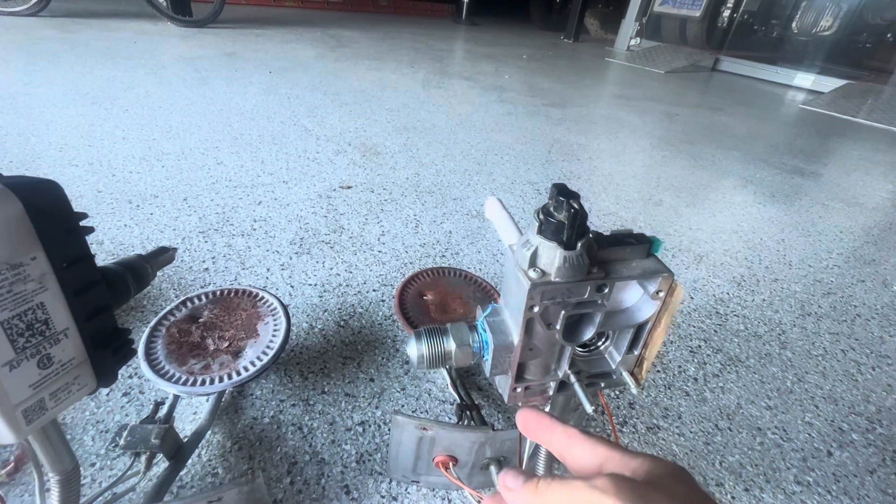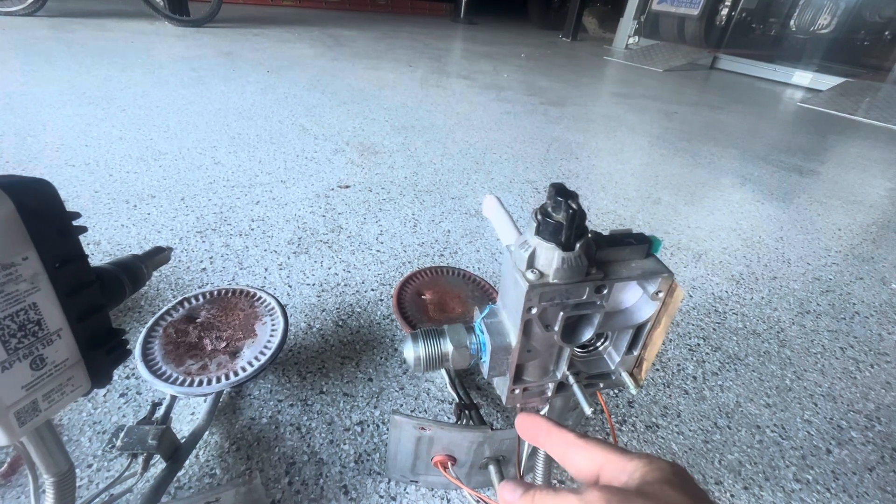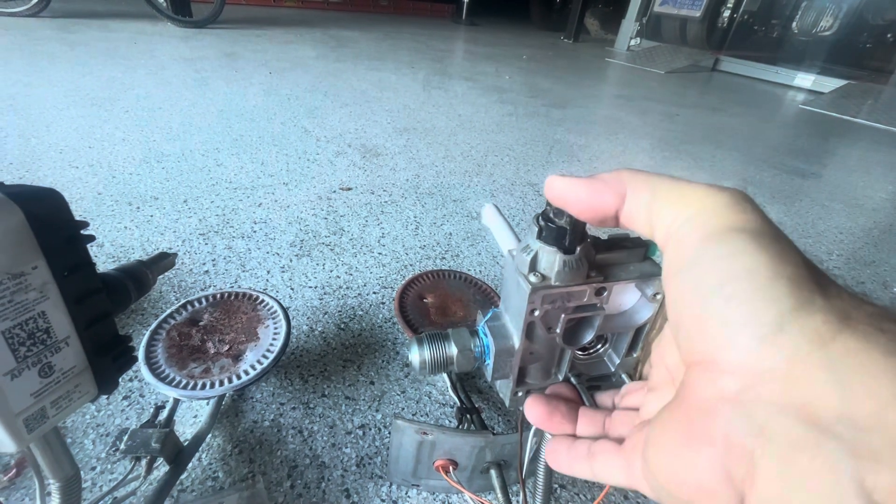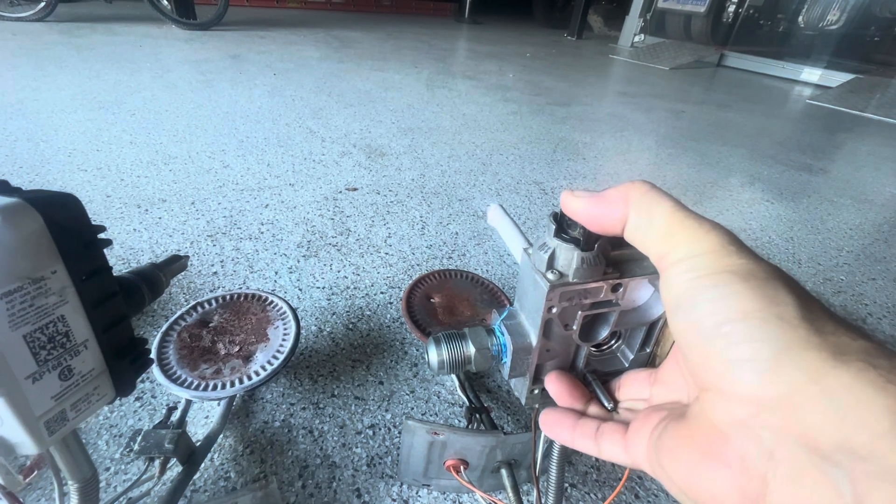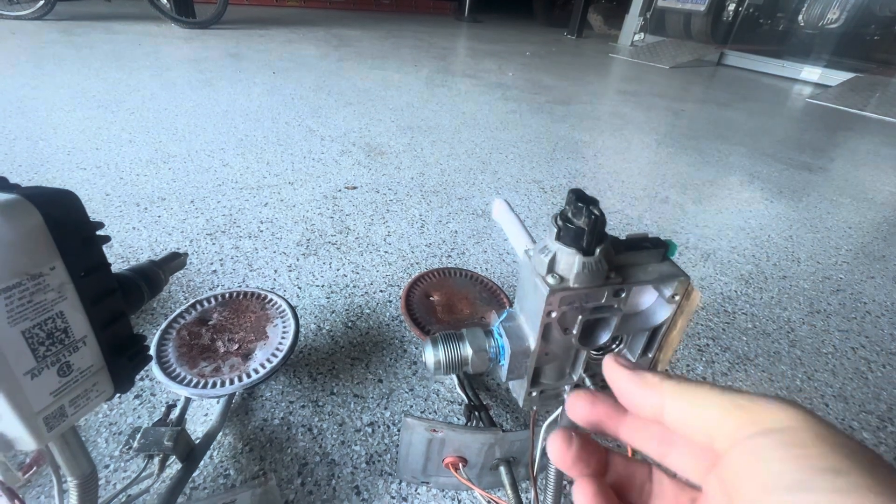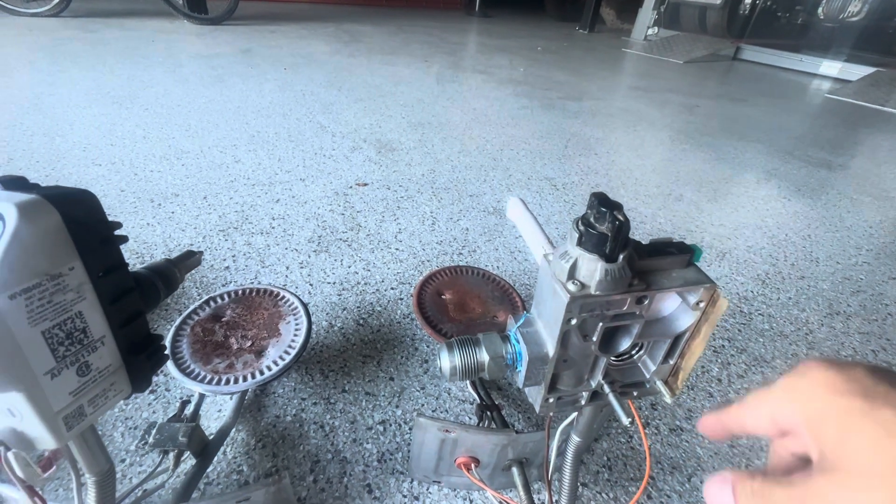Anything over 13 millivolts and it'll typically level off between 20 and 27. That mag assembly now has enough magnetic power to hold itself down. When you release, it stays open. That lets the gas go down to the pilot.